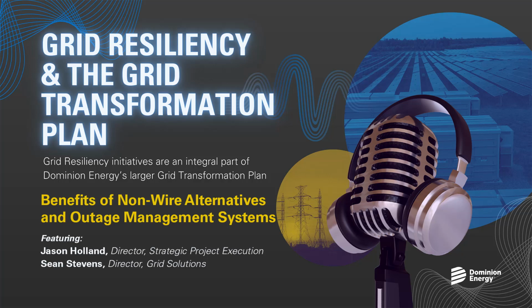Yeah, absolutely. Hanover substation was really our first opportunity to install a non-wires installation, part of the original 30 megawatts of our GTSA energy pilot. With this installation we evaluated the ability for an energy storage system to be placed inside a substation and reduce the peak load on that substation transformer. We commissioned the battery in 2022 and successfully demonstrated that the battery can discharge during peak time to reduce load on the transformer, which in turn potentially extends the life of the transformer.